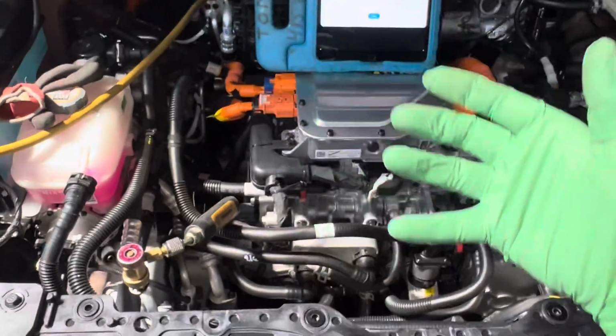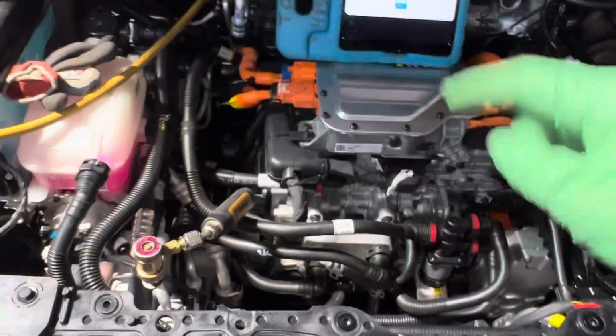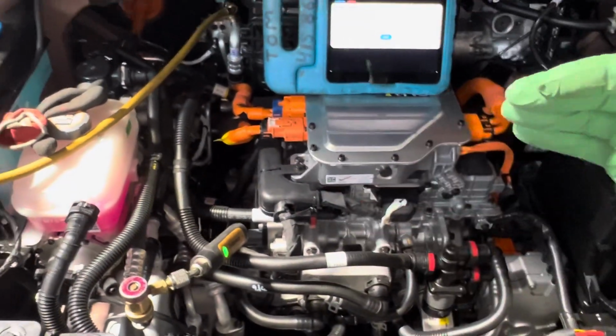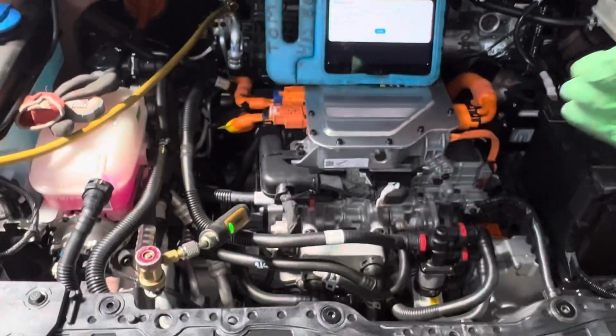They'll have a service mode, and if you don't go through that mode, you can trap refrigerant in different parts of the circuit because the hard shutoff solenoid valves could be in the closed position, and then you think you got all the refrigerant out, but you actually don't.